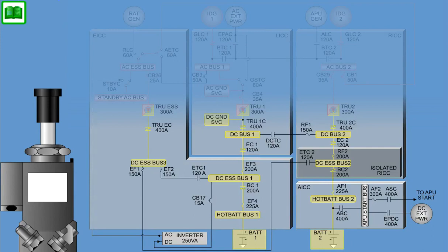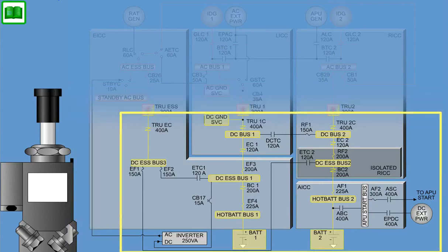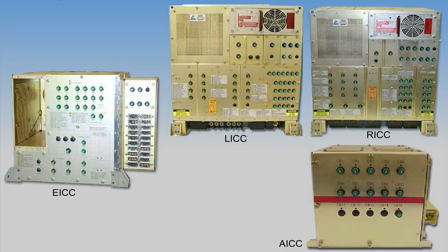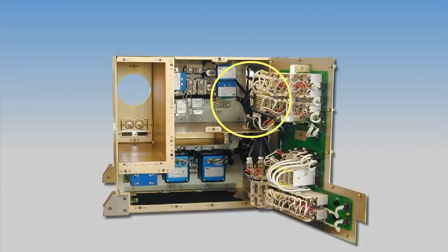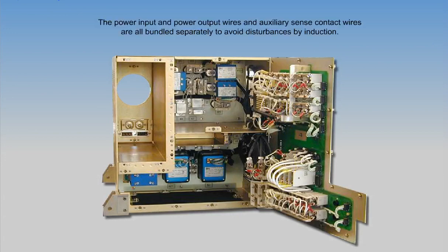The DC circuit breakers provide protection of supply lines and cables for loads whose power is sourced from the DC supply system of the airplane. The circuit breakers are mounted on the circuit breaker panels located on the front of the left, right, essential, and auxiliary integrated control centers. Only DC circuit breakers are mounted on the AICC. The feeder wire bundles and load output wire bundles to the DC circuit breakers are separate from the wire bundles to the AC circuit breakers. The power input and power output wires and auxiliary sense contact wires are all bundled separately to avoid disturbances by induction.